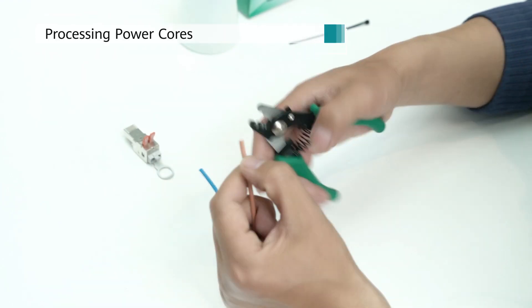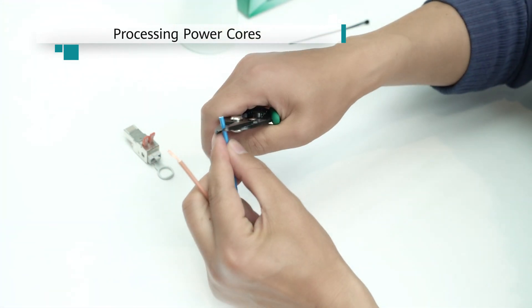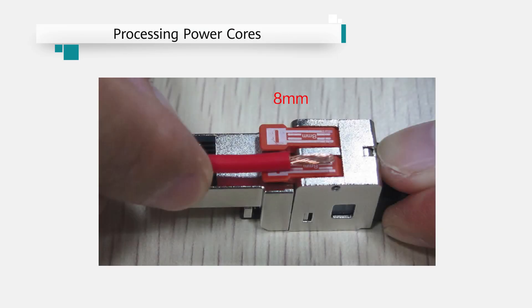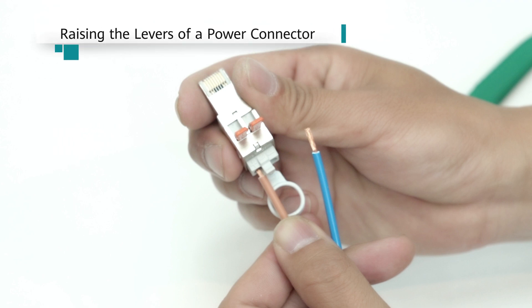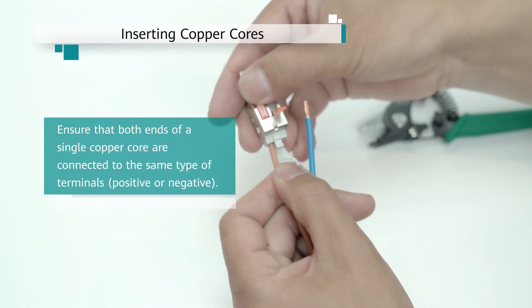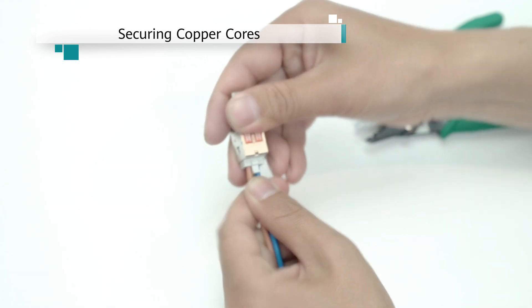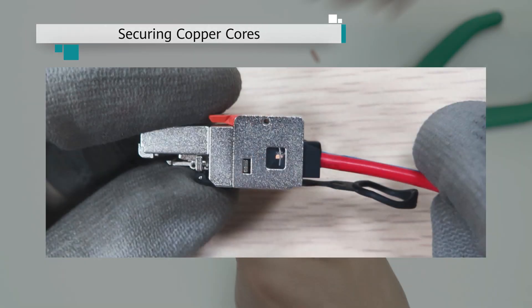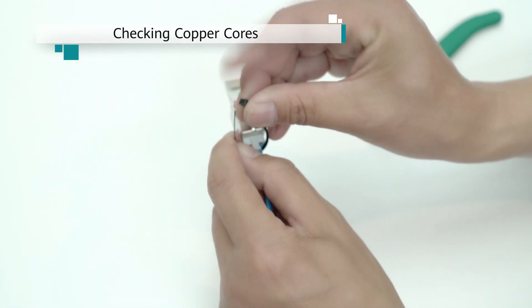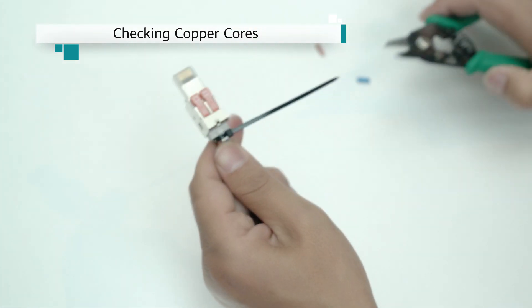Assembling power cores. Peel 8 mm of insulation coating off each power core. Fully raise the levers of a power connector. Insert the copper cores all the way into the cable inlets, ensuring that no copper conductors are bent or exposed. Lower the levers and look through the observation windows to verify that the springs do not overlap with the insulation layers. Pull each copper core with a force of about 10 N and ensure that each copper core is properly connected. Bind the copper cores with cable ties in the same direction and cut off the excess cable ties.